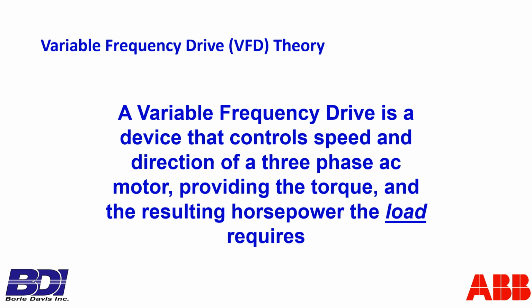So what is a variable frequency drive? Well, it's a device that controls the speed and direction of a three-phase AC motor. We drive three-phase AC motors, and we provide the torque and the resulting horsepower that the load requires. I've underlined and italicized load simply for this reason. Drives and motors are simple devices, really. They know they have to deliver what that load requires.